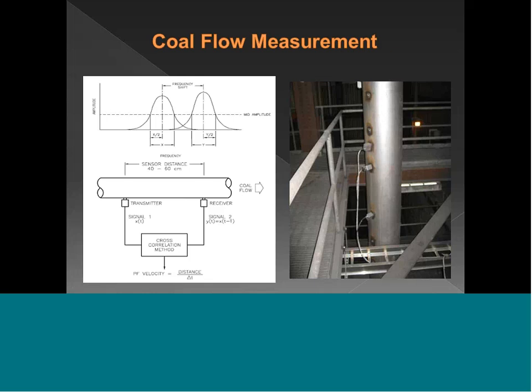Now, the reason for the third sensor: in some cases, these sensors from a mass flow standpoint have to be 1.5 diameters apart from a microwave standpoint to measure this mass. If we were in a 12-inch diameter pipe, that would be 18-inch spacing. Now we're trying to cross-correlate something across 18 inches, which is very doable. As we get into a 24-inch diameter pipe, now we've got 3 feet of spacing between those antennas. The cloud of coal dust changes too much across that 3 feet, and so cross-correlation isn't that simple. So in large diameter pipes, we use a third antenna, so that the upstream two antennas are measuring the mass of coal, and the downstream two, these two here, are measuring the speed of the coal.